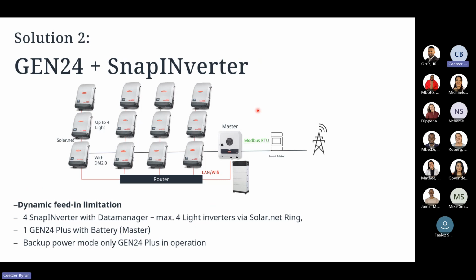If the client has a Gen 24 Plus with a battery and they have multiple snap inverters, again, the master becomes the Gen 24 because it has a pilot device and also it has got the battery communication to it. Again, you'll need to make sure that we have the smart meter communicating directly, and we'll need to make sure that we have only 4 snap inverters with the data manager that are then communicating directly to the unit itself. So if we have got 12 snap inverters in the system and we've only got 1 data manager existing, we would then need to make sure that we have an additional 2 data managers, in order to complete the loop correctly, and then allow the communication back to the master with the battery itself.